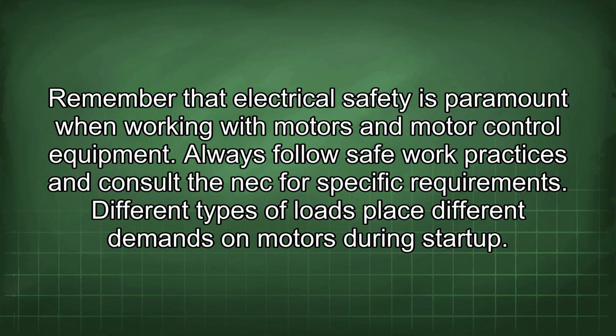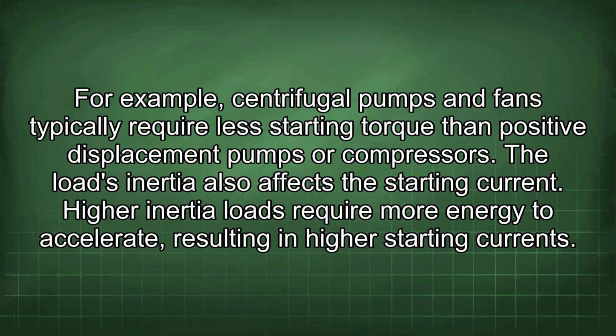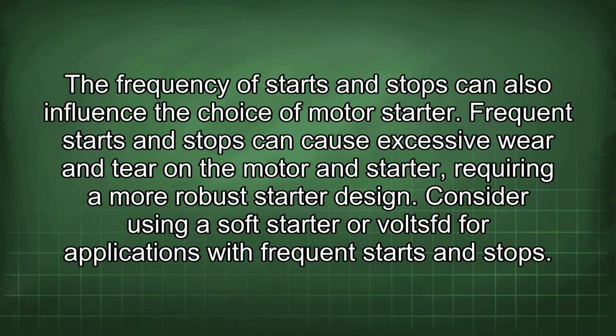Different types of loads place different demands on motors during startup. For example, centrifugal pumps and fans typically require less starting torque than positive displacement pumps or compressors. The load's inertia also affects the starting current. Higher inertia loads require more energy to accelerate, resulting in higher starting currents. The frequency of starts and stops can also influence the choice of motor starter.